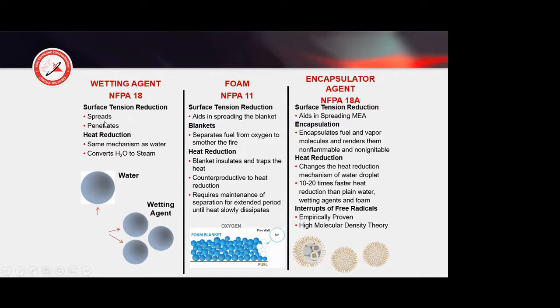But when you look at the heat reduction, you have the same mechanism as water. It's a steam conversion. So because you have a wetting agent with reduced surface tension, you'll get some smaller droplets automatically as a function of the surface tension reduction, which means you have a little more surface area, which means you'll end up getting more steam conversion. You'll have a moderately better heat reduction than plain water. The downside is you'll create much more superheated steam. It's something that the firefighters and most health and safety engineers don't like: additional steam.